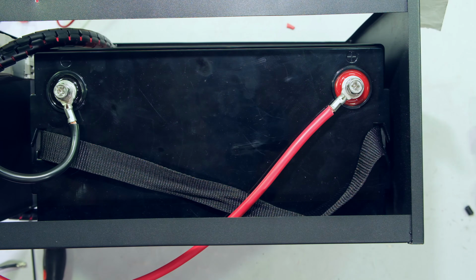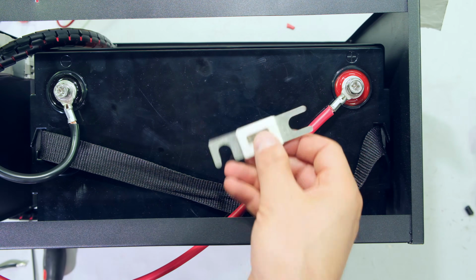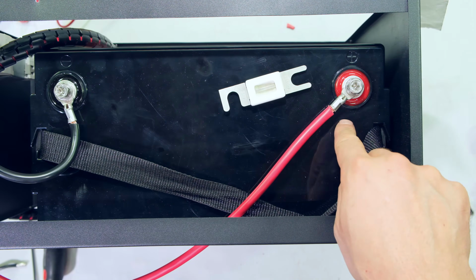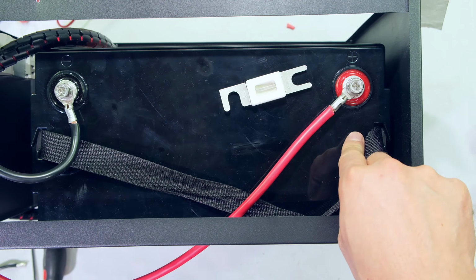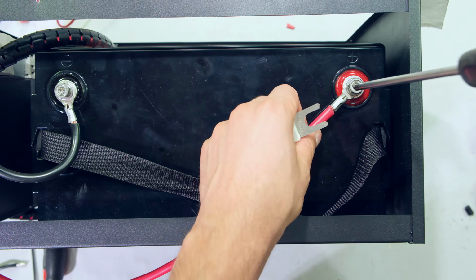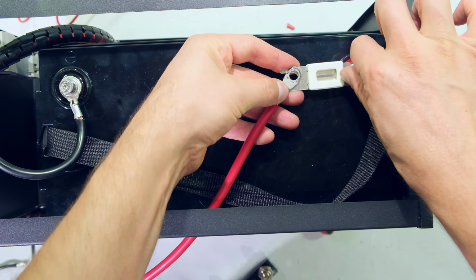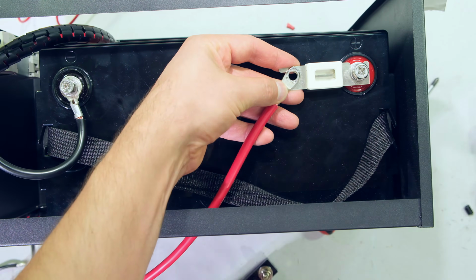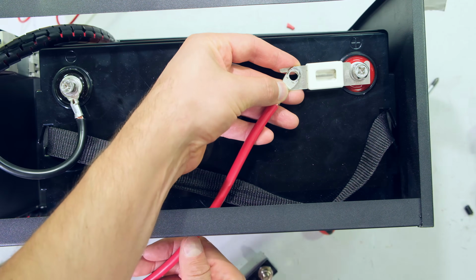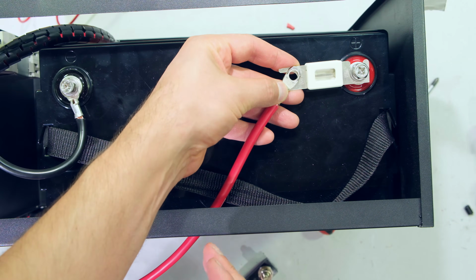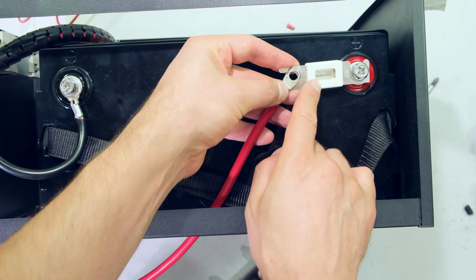Now, say for example, you wanted to just use fuse protection. You could put a fuse, and the fuse should be as close to the battery as possible. So in this case, if I was going to fuse this battery, the fuse would sit like that, and then I would use a nut and bolt on this side. Therefore, if anyone shorts the battery cable, or the inverter has a fault, or the circuit breaker does not trip, the fuse will blow.